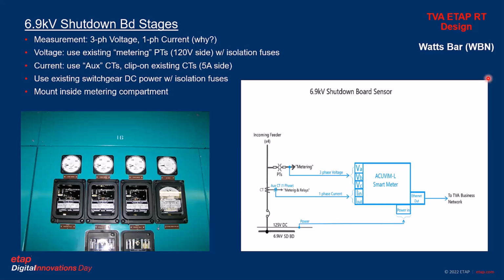Here's a detailed view of what the 6.9 kV shutdown board sensor connections will look like. We're using 3 phases of voltage to connect up to the metering PTs. We're only going to use 1 phase of current, and really the reason there is just it saves a lot of connections. And these smart meters are capable of calculating the 3-phase power from either 3, 2, or 1 wire connections. So we're going to use the 3-phase voltage so we can have the voltage balance measurements available to us, but we're only going to use one phase of current.